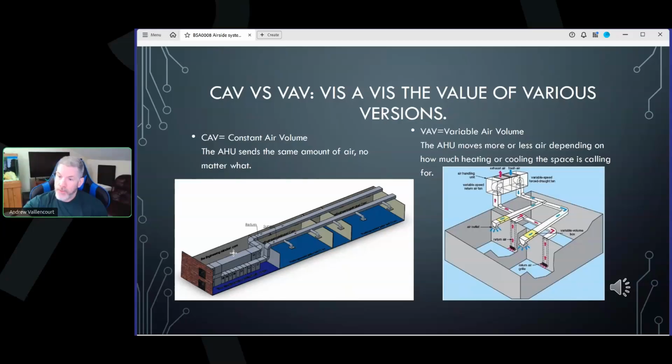But all through the 90s and early 2000s, when utilities were giving VFDs away, constant volume air handlers were getting VFDs installed, the sensors were put on, the contractors were making money, the utility was able to show that they were spending customer money on these energy saving devices, and they didn't do a darn thing. And nobody is ever happy when I bring that up.